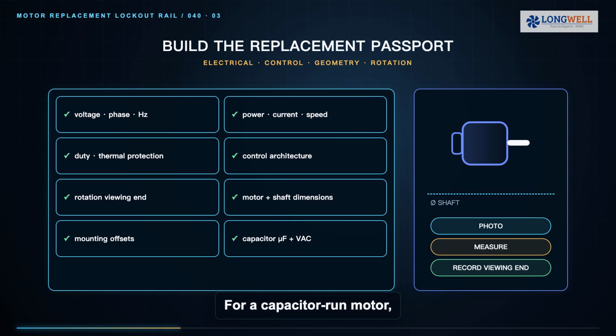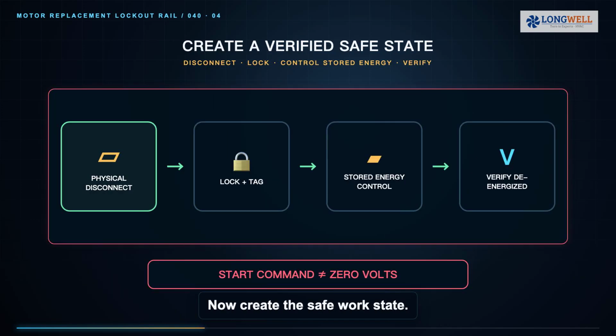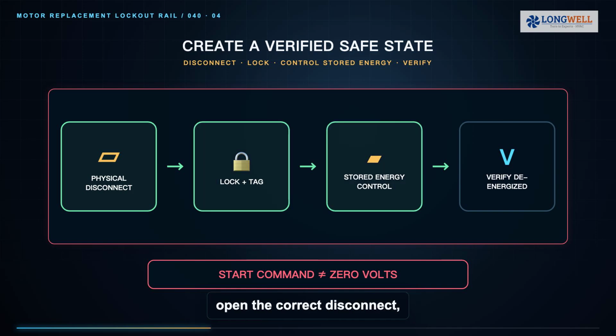For a capacitor-run motor, record the specified capacitance and voltage rating. Mark the wheel's axial position on the shaft and note which side faces the inlet. Wire color is not a universal standard; the equipment diagram is the authority. Now create the safe work state.